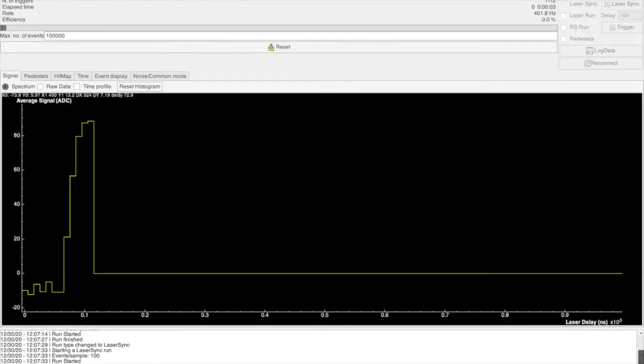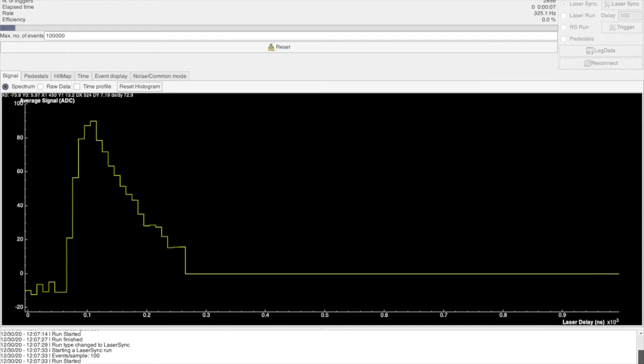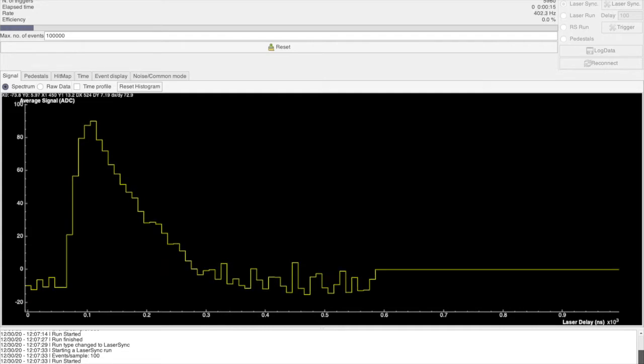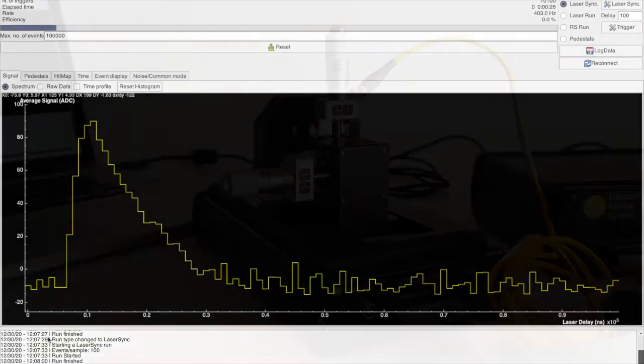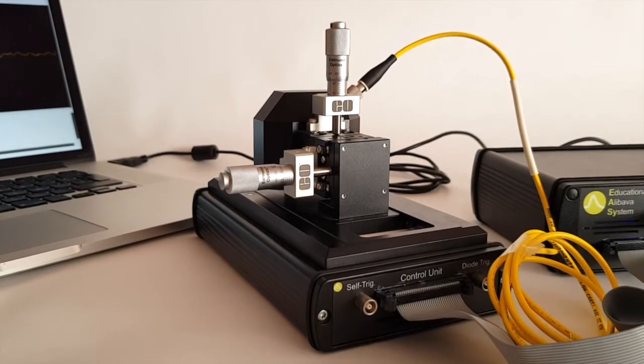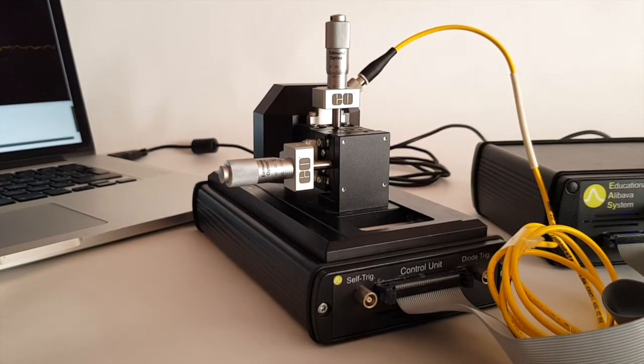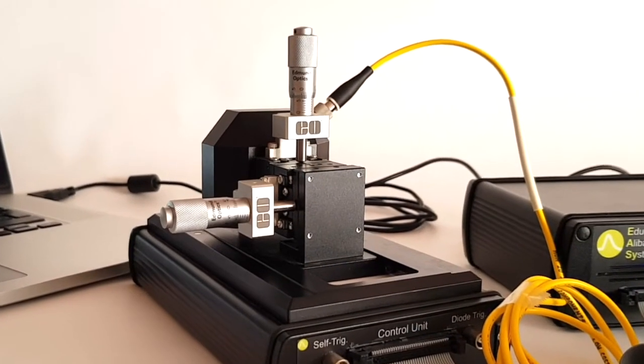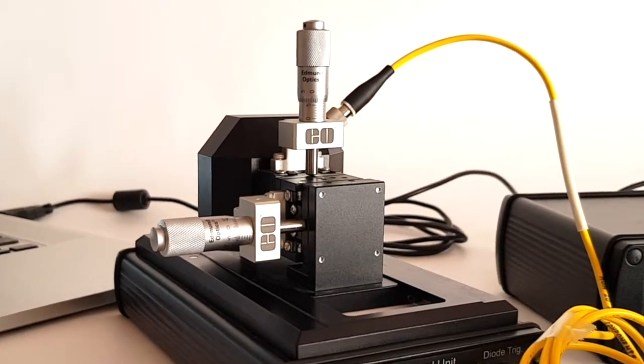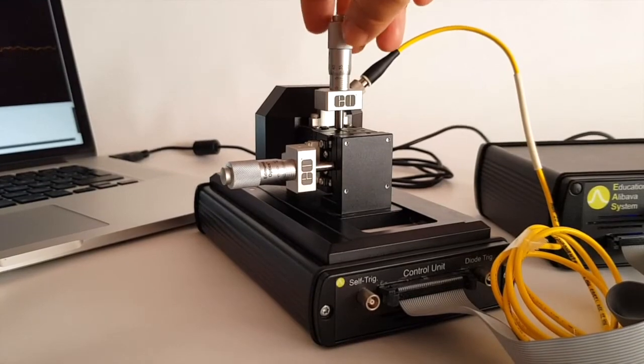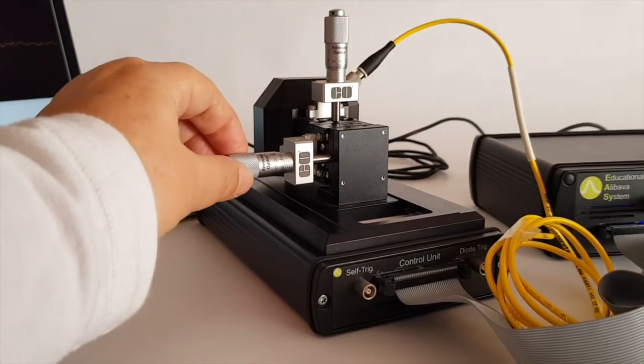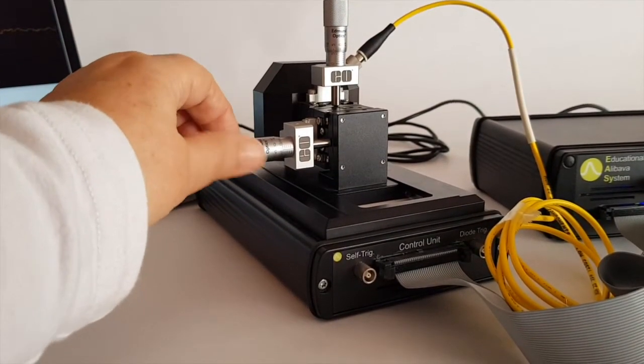The laser synchronization scans the delay between the pulse sent by the control unit and the data acquisition, so that the system can sample at the maximum of the signal produced by the laser. The delay corresponding to the maximum of the peak is 100 nanoseconds. Once the delay has been set, we can proceed to focus the laser. The laser beam is focused using the two micrometric screws that move the laser up and down over the microstrip detector and in the horizontal plane, perpendicular to the direction of the strips.